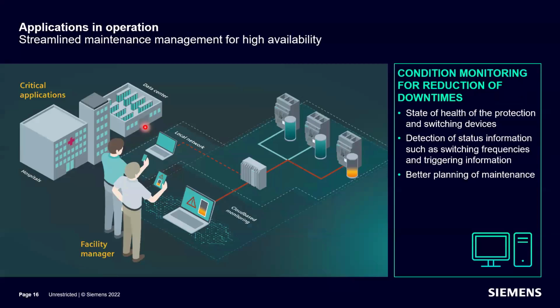There's condition monitoring available with it. Condition monitoring is something with the devices - ACB and MCCB are probably where we need a change if there is consumption of its complete life cycle. So if the devices have certain features available in the Sentron portfolio of Siemens, my device has a complete life cycle consumption tracked. I will get info through this IoT device that the device has a remaining lifetime of, say, 1 year or 2 years, where I need to change the device.